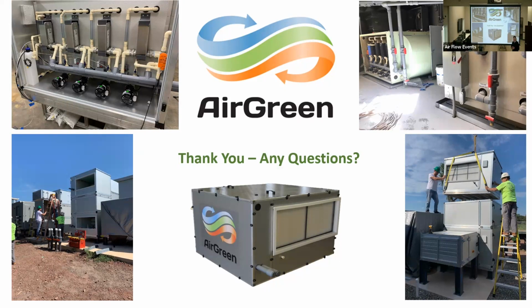That's a lot of dehumidification at 15,000 CFM. It is, and since people are used to dehumidifying with airflow, they get locked around, well, if I'm going to dehumidify, I need this much. And actually with a desiccant system, you don't. That's a little bit of an education we have to go through, saying, give us the load, we can tell you what airflow you need. For the cannabis guys, they want circulating air, so a lot of times we're circulating air with no chilled water anywhere in the system. That's fine, because they want the circulating air. I don't think we need to get bigger than 15,000, but some of the large pharma units are used to those numbers. And we'll figure out the right place to be.